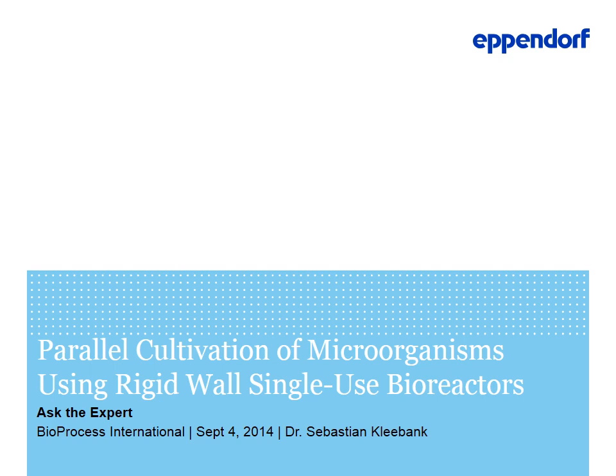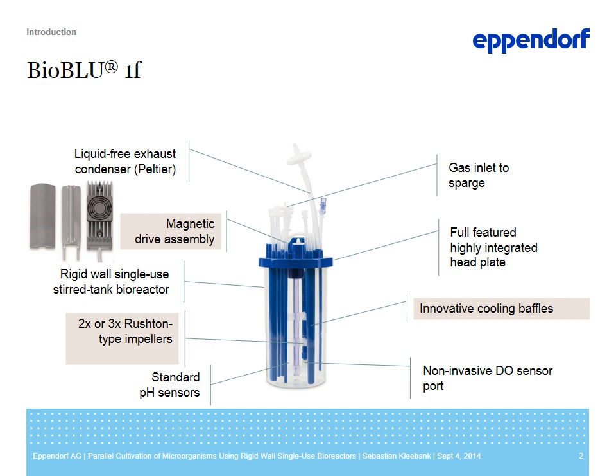Today I would like to introduce our new single-use bioreactor for microbial applications, the BioBLU 1F. On this slide you see a picture of this bioreactor. The bioreactor has a gas inlet filter for sterile gas supply. It has a fully featured, highly integrated head plate and innovative cooling baffles for high mass transfer and high cooling capacity. Also, this vessel has a non-invasive DO sensor port. This means the DO sensor is not in direct contact with the medium because there's a silicon membrane at the bottom.